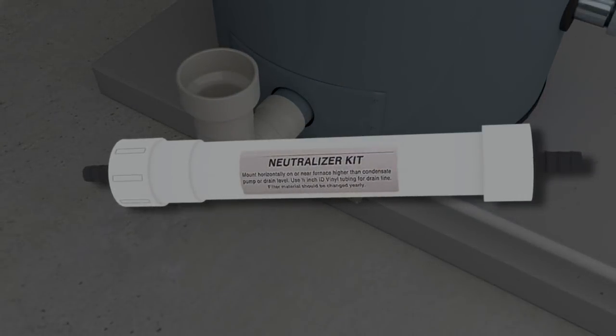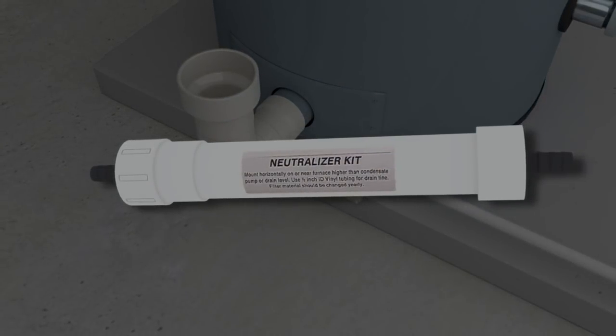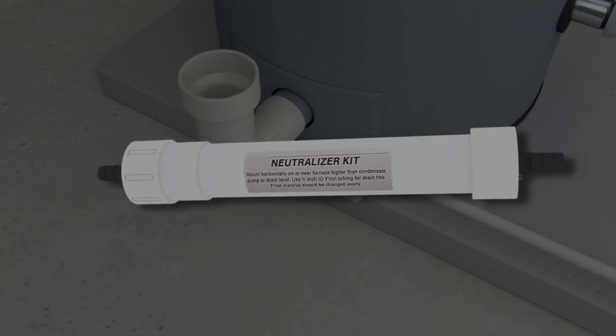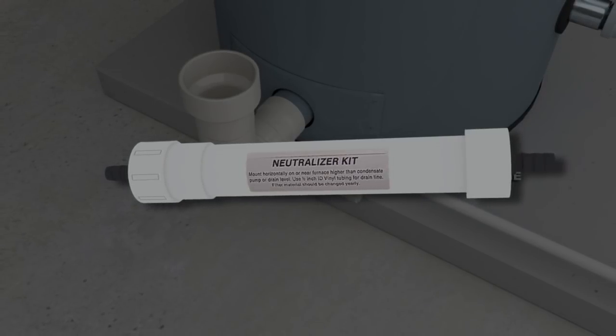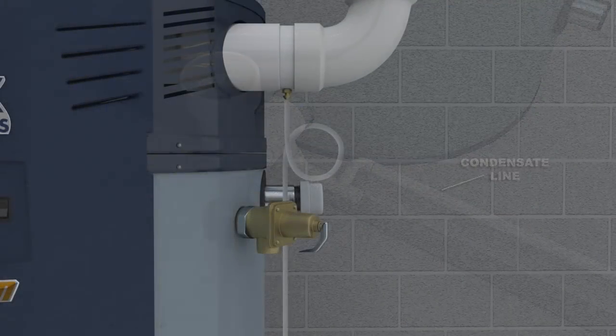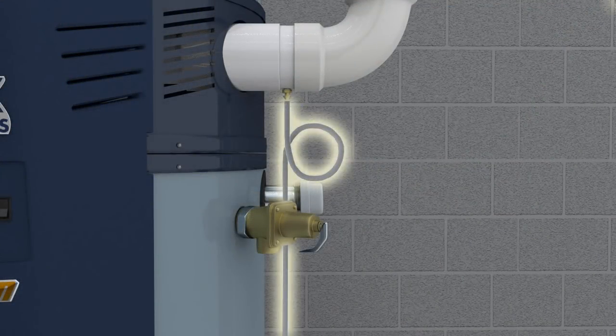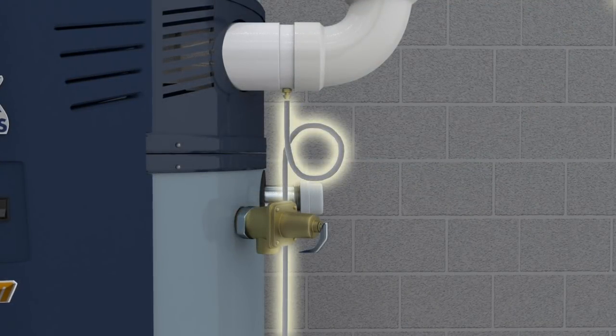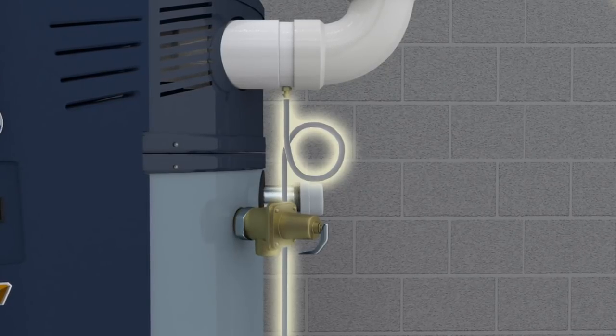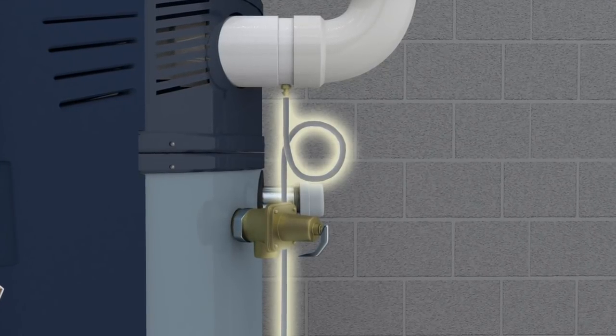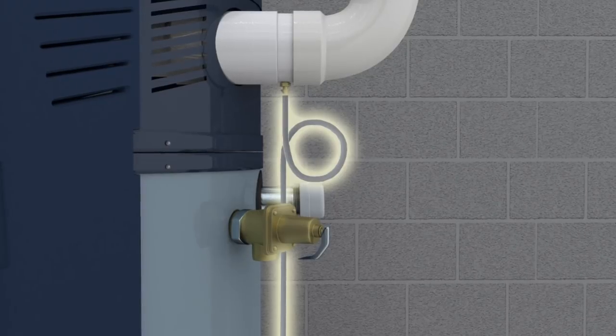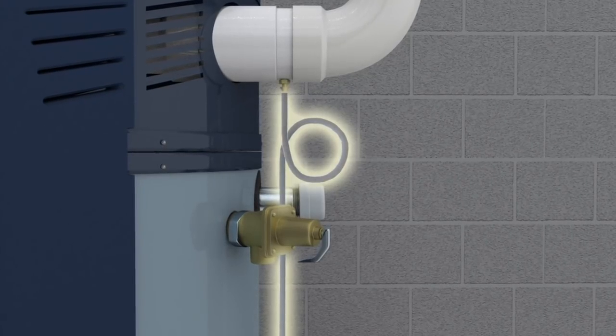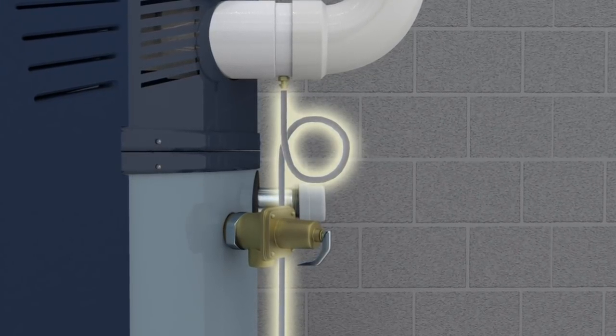Due to the acidic content of flue gas condensate, some local regulations may require that a neutralizer be installed prior to the drain. A second condensate drain and trap may be installed on the air intake of the direct vent if the vent is vertical or cannot be sloped away from the water heater. This intake drain helps to prevent buildup of condensate during standby periods.